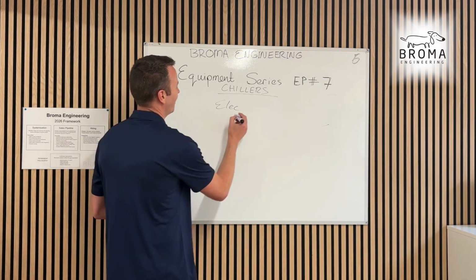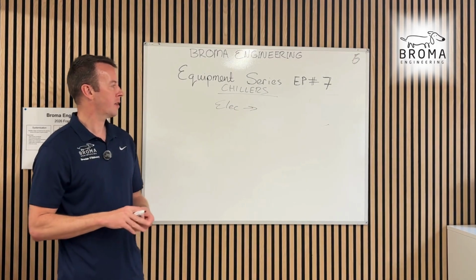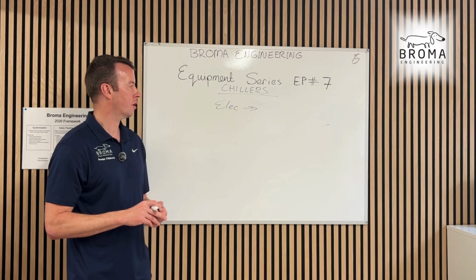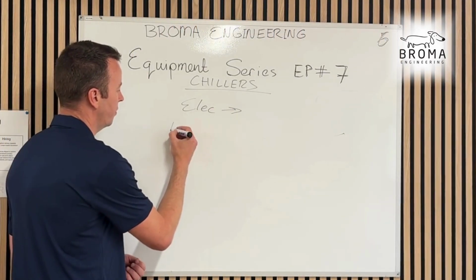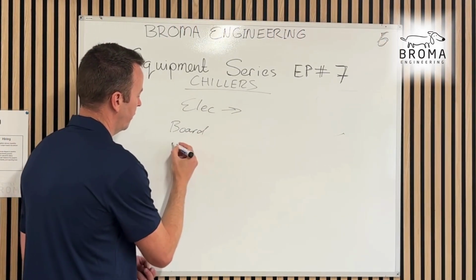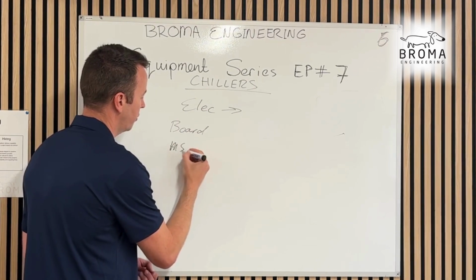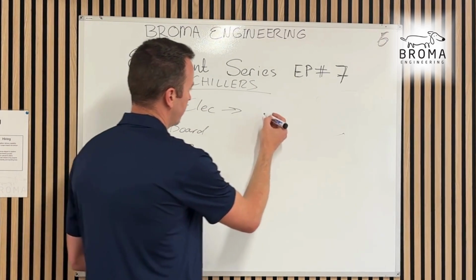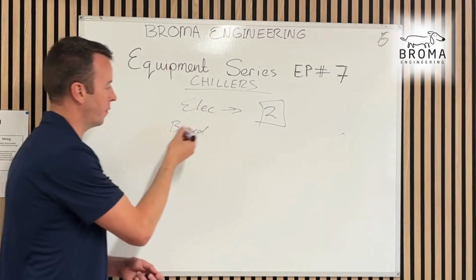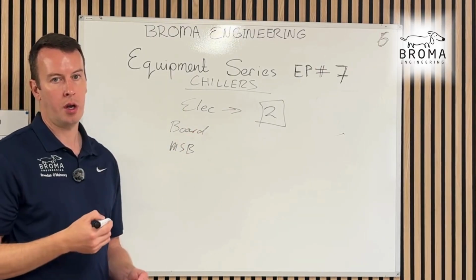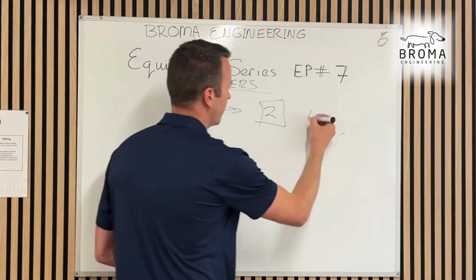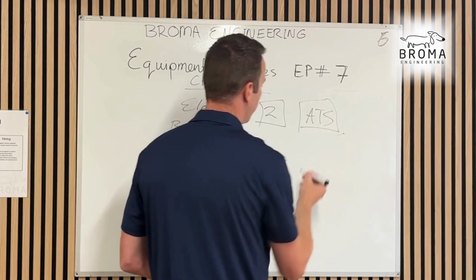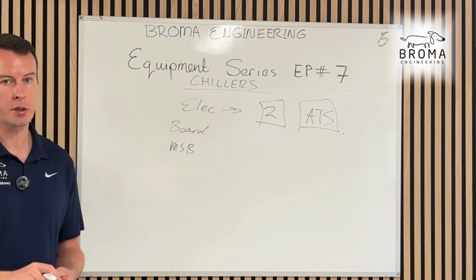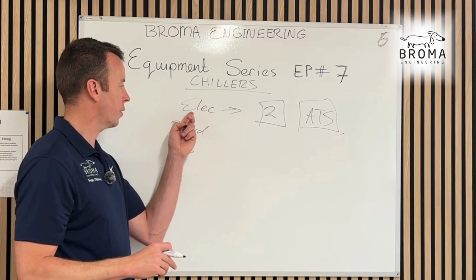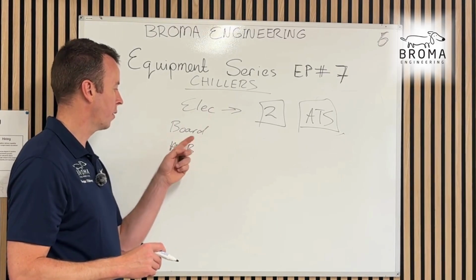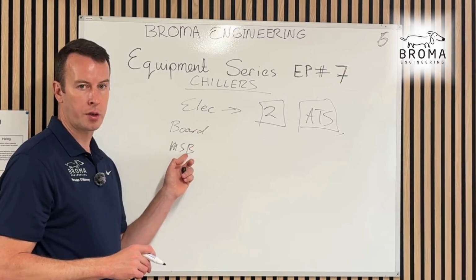Sorry for that. We need to test the LV cables coming to the chiller, and we need to know where the board is downstream and where the board is upstream. It might be the main switchboard on that string. There might be two supplies, so be careful. There'll be different strings for redundancy, and there might be an ATS, automatic transfer switch, that'll have to be commissioned also. There'll be breaker settings. You'll have to talk to your electrical colleagues, or the electrical team need to know when they'll have the upstream boards ready so they can cascade power down to you.